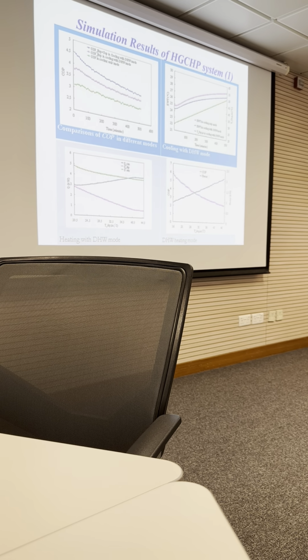You see, there are three curves. The blue one is the COP with domestic hot water supply. The pink one, heating with domestic hot water mode. Then the green one, cooling only mode. You see? If we have hot water supply, even for heating and for cooling, the COP is much higher. Especially the blue one, you see, it's more than 3 or 4, sometimes even 4.5. But if no hot water supply, it is less than 3. If the COP is less than 3, we say it's not efficient.